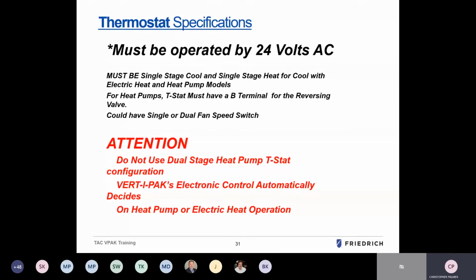In the event that there's a long-term call for heat and the heat pump itself is not maintaining temperature in the room, the control will drop out the heat pump and energize the electric strip. The electric strip and the heat pump will never run together simultaneously at the same time.